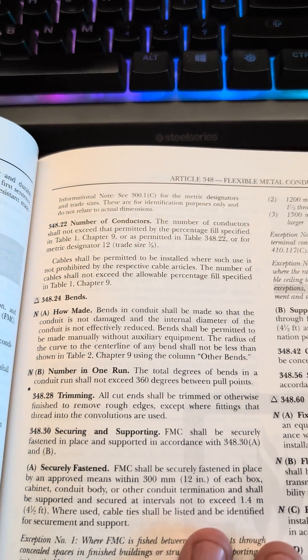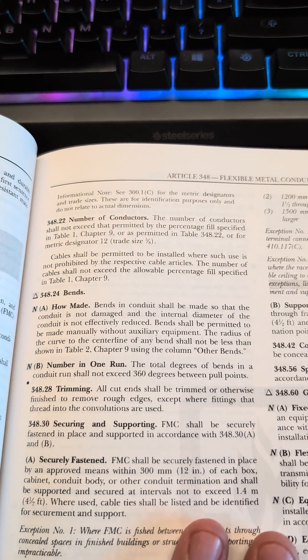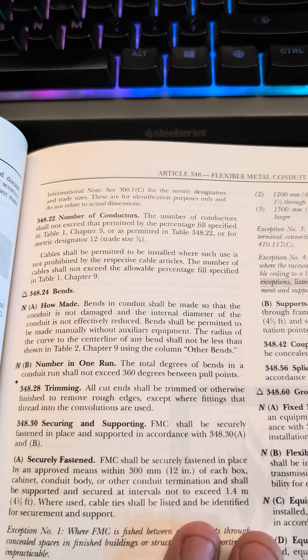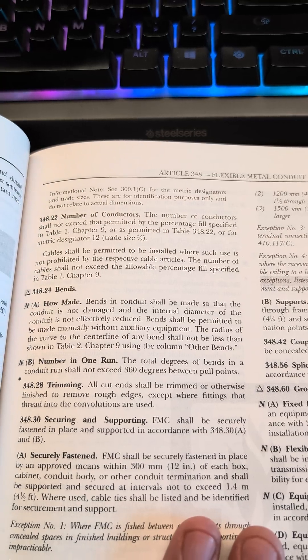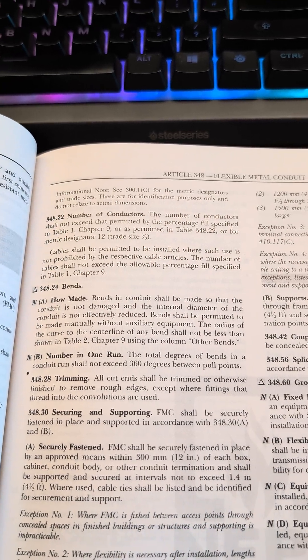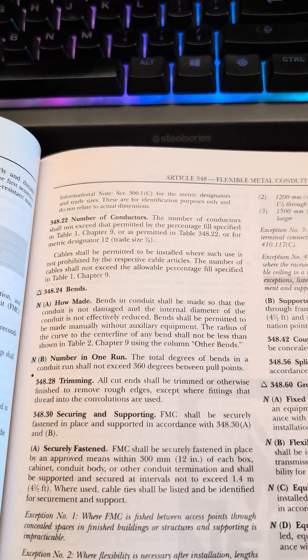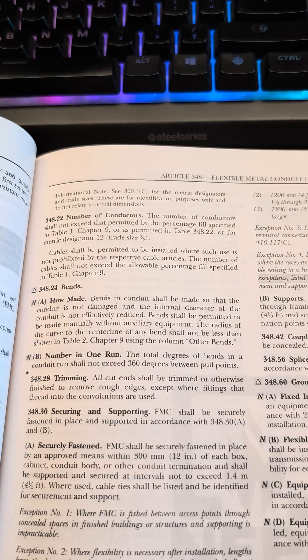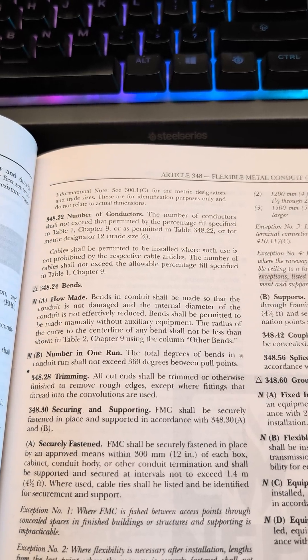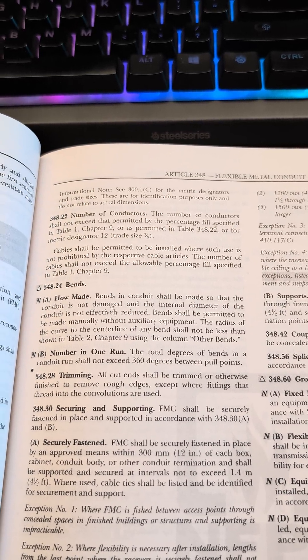and then there's number of conductors. The number of conductors shall not exceed that permitted by the percent fill specified in Table 1, Chapter 9, or as permitted in Table 348.22 for metric designator 12, trade size 3/8.